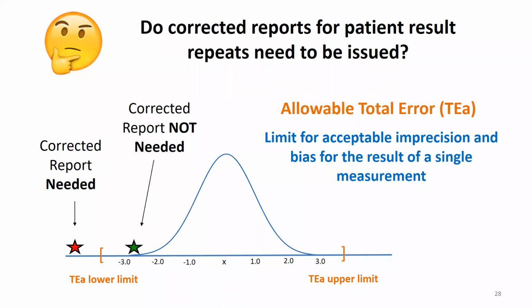by the green star, corrected reports do not need to be issued because a clinically significant impact of the error is unlikely. However, if the original erroneous values fall outside the allowable total error limit, as shown by the red star, then a clinically significant impact of the error is likely and corrected reports need to be issued.